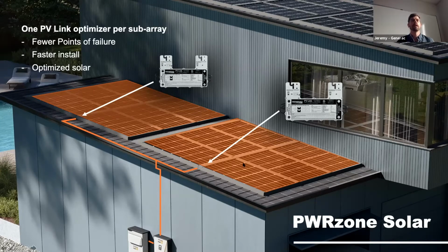If you're using an MLPE system, a module level power electronic system like a microinverter or a per-module optimizer, you would need one of those devices per panel. We just have, in this case, 1 per 6. Sometimes you can get as many as 8 or 9 panels onto a single PV link, usually as few as 2. So a lot less equipment on the roof in this system.